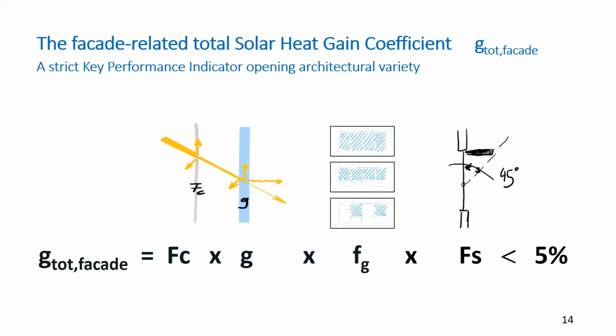I say to them, solar shading and solar heat gains are driven by a multiplication of only four factors. The first is the G value of the glass, so the solar heat gain coefficient of the glass. The second is the shading effect from your shading system. The third one is the question, how big are your windows? So the factor, the proportion of the windows in the facade. This is the drawing of a big glazing, of a semi-big glazing and a small glazing. And the fourth, natural shading effects, so the shading effects of buildings, of overhangs, of fins, maybe of trees. These four factors, multiply them together and look at the outcome.